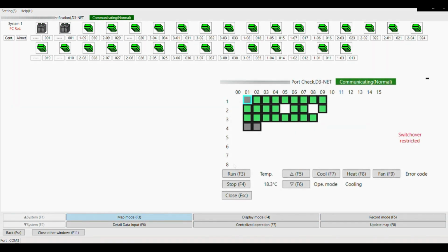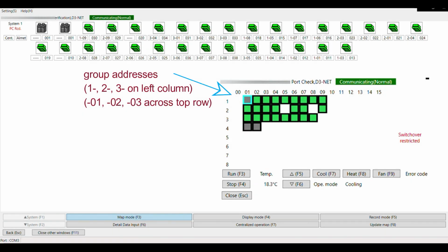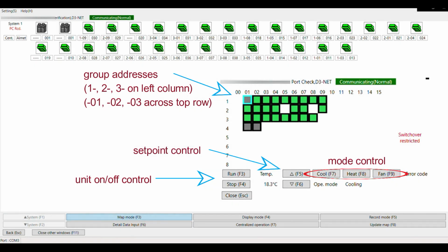From here, we can click on each group address, turn on or off the unit, change mode of operation, and adjust the set point. It's important to note that regardless if you selected Fahrenheit in the settings at the beginning of this video, this particular window will always display the set point in Celsius. There is still, after I don't know how many years, no fix for this, so we're stuck using Celsius.